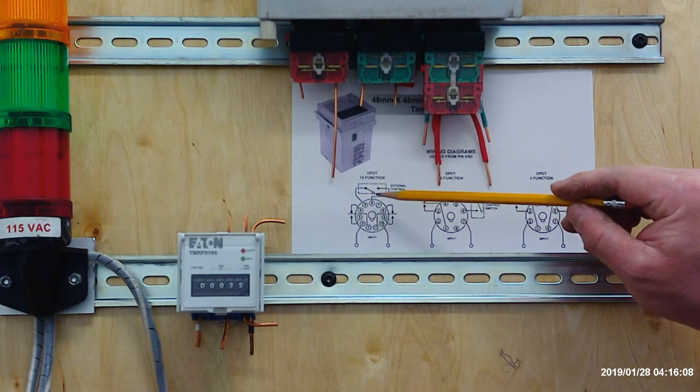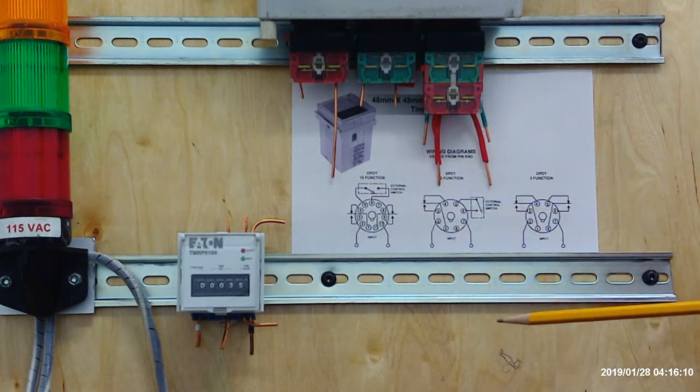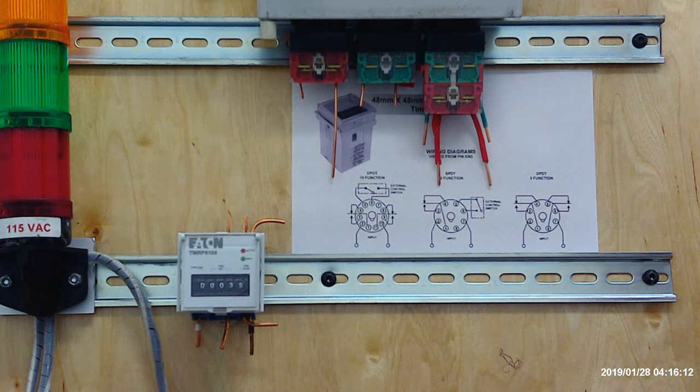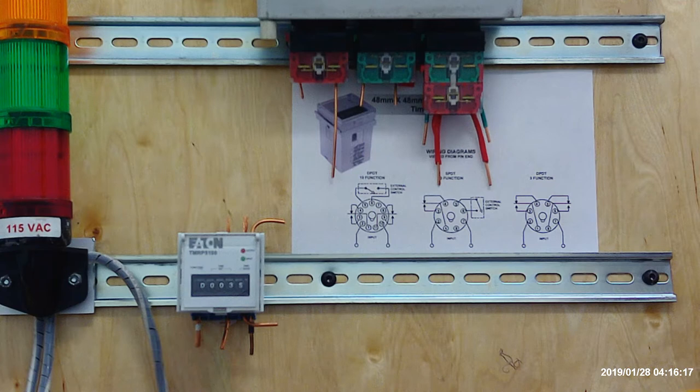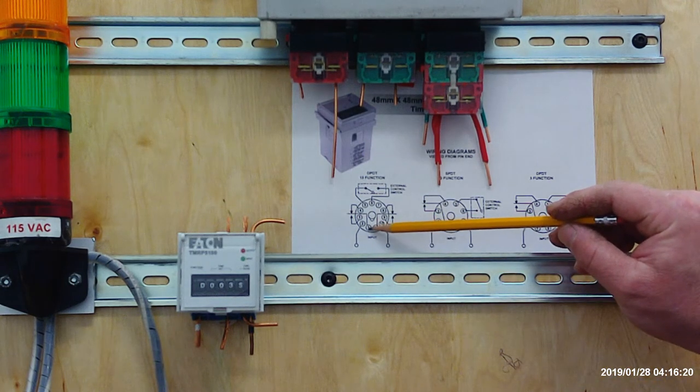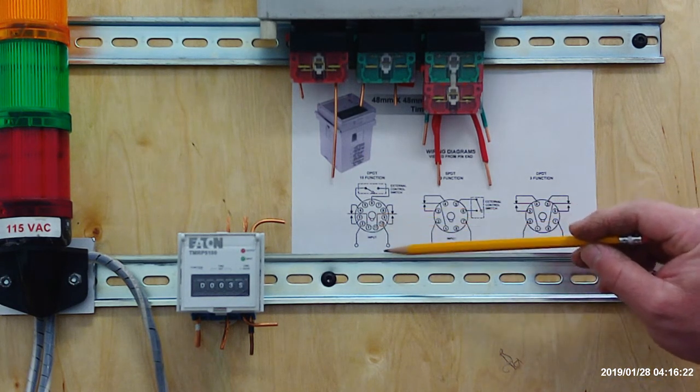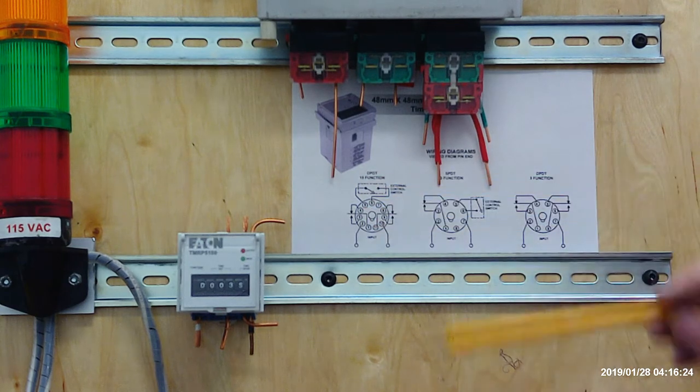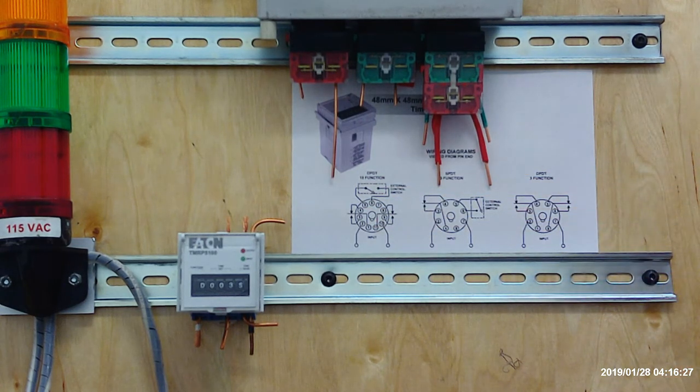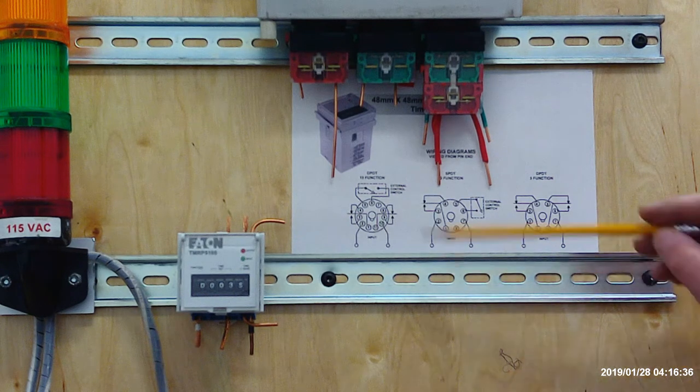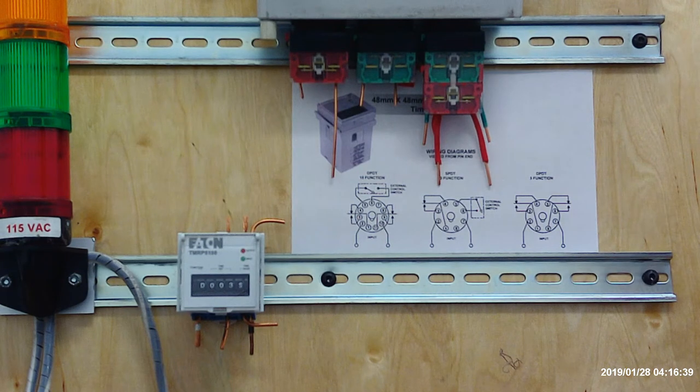Well how does this thing work? You have an external control switch that once you close the circuit and provide energy, it'll actually alter the state, closing from the one to the three and then opening the contacts from the one to the four. The important difference between the off-delay timer versus the on-delay timer: the off-delay timer doesn't start timing until you open up the external control switch.